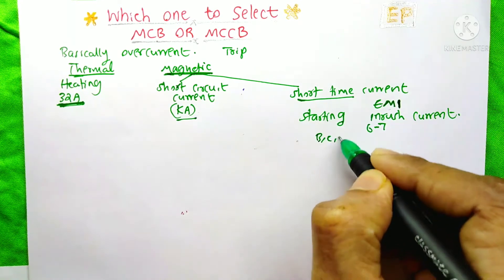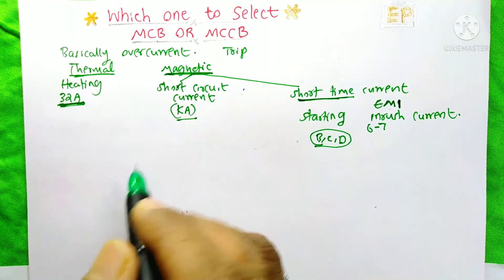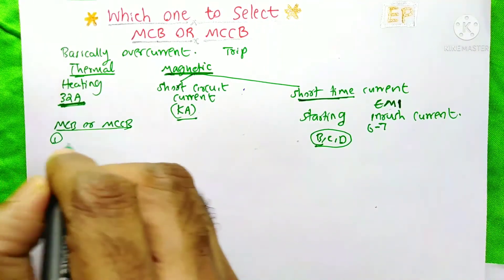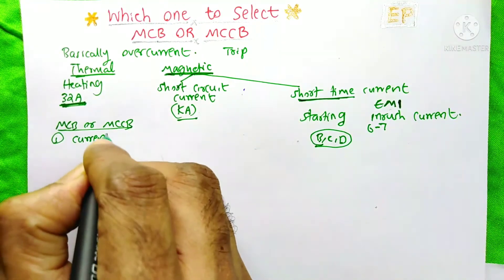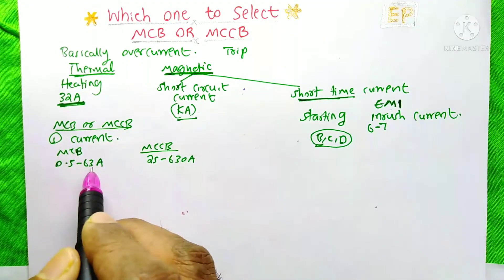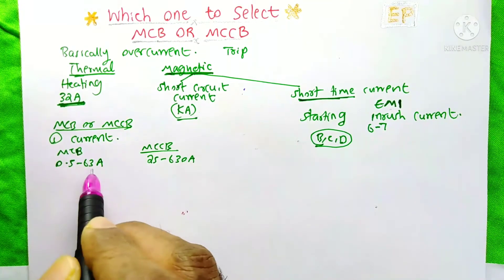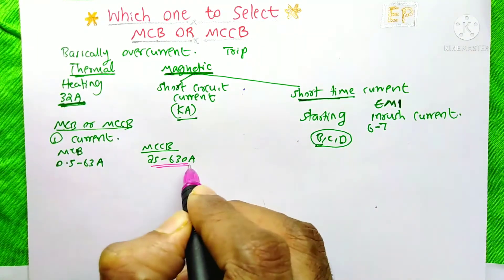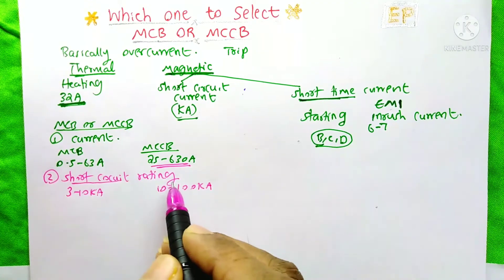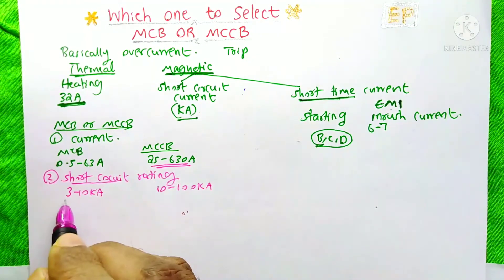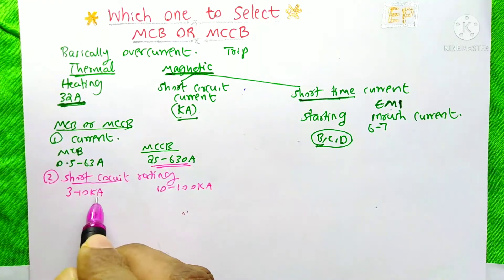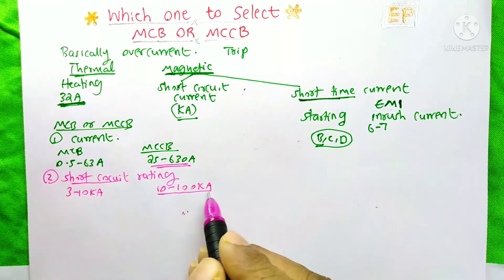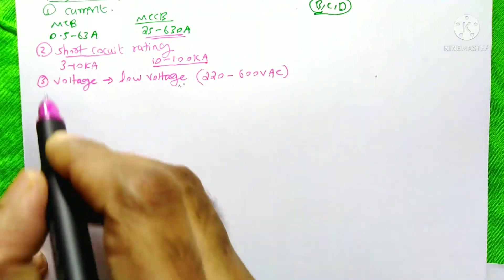For selecting MCB or MCCB for our application, the first factor to consider is the current range. The MCB is available from 0.5 to 63 amperes, while the MCCB is available from 25 to 630 amperes. The second factor is the short circuit rating: the MCB is available from 3 to 10 kilo-amperes, but the MCCB covers a higher range of 10 to 100 kilo-amperes.